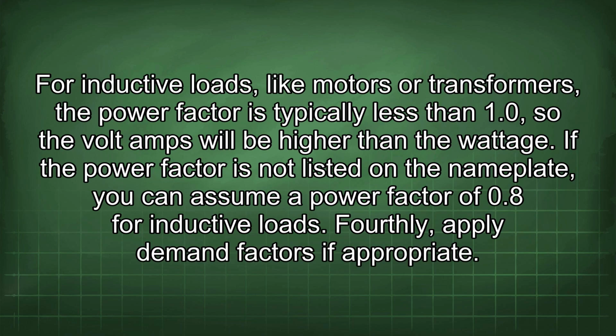For inductive loads, like motors or transformers, the power factor is typically less than 1.0, so the voltamps will be higher than the wattage. If the power factor is not listed on the nameplate, you can assume a power factor of 0.8 for inductive loads.